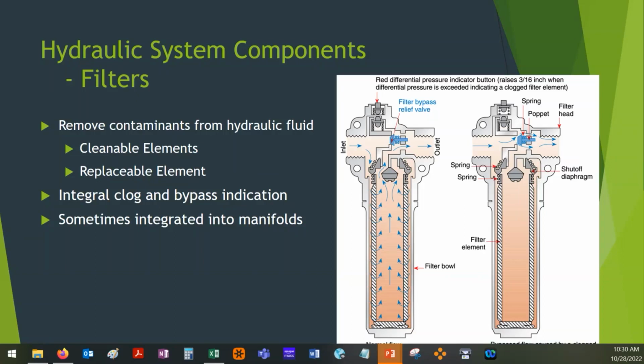So you see the first one popped. Okay, we need to clean the filters. We need to put clean filters in there. Hopefully that's all it was. You see the second one popped. You say, uh-oh, we had dirty fluid running through the system. Now you've got to do a little bit more maintenance action on it.